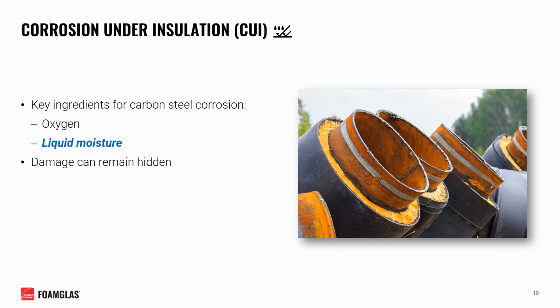Another byproduct of introducing moisture underneath your insulation system involves the potential for corrosion under insulation, or CUI, to occur. Some key ingredients for the corrosion of carbon steel include the presence of oxygen as well as liquid moisture. Oxygen is almost always readily available, whether it be from the air or dissolved in water itself. So once condensation takes place and liquid moisture becomes readily available, you do become at risk for corrosion to begin occurring. Corrosion can damage the outside of the pipes over the span of multiple years and can remain hidden and out of sight until it's well too late, in the most catastrophic instances, resulting in failure of your entire piping system in general.